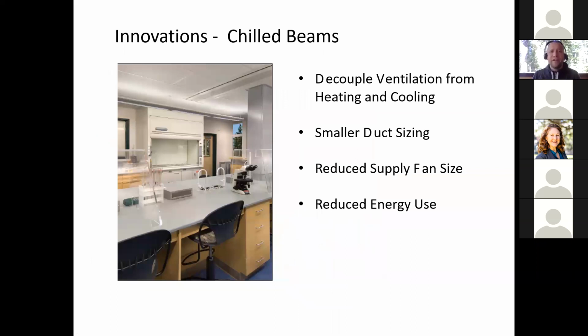We love chilled beams, especially for lab projects or other high load spaces, because we can get a lot of cooling and heating out of a relatively small system. In the image on the left you can actually see a chilled beam, it's this piece next to that column. You'll see a little grill and a little slot that the air blows out of, but it's very reserved, not very noticeable. It's a pretty shallow element, but it allows us to do all the fun things we love about decoupled systems.